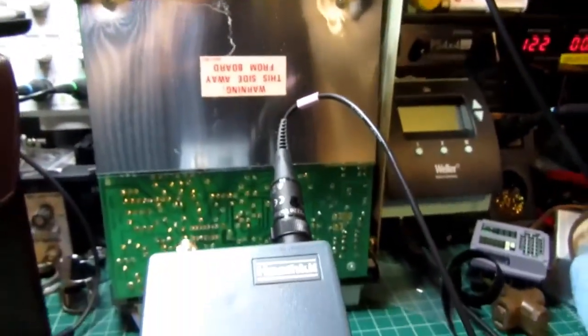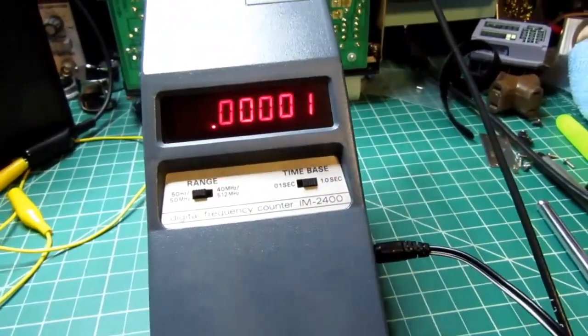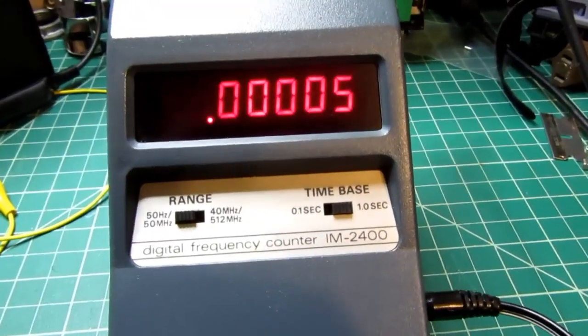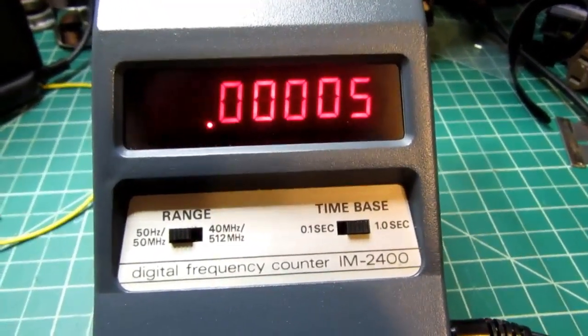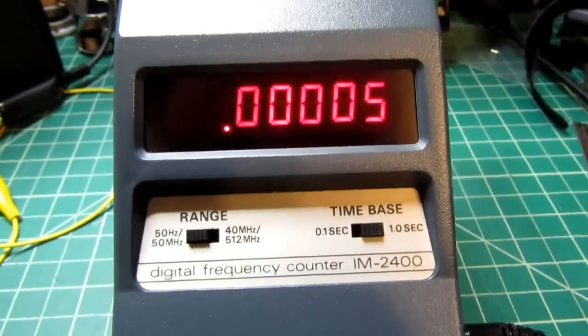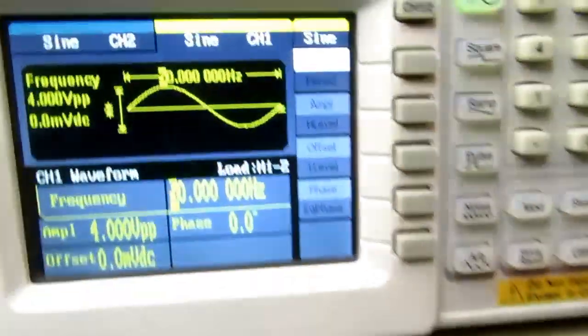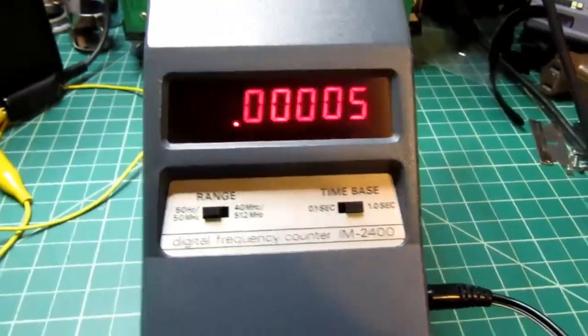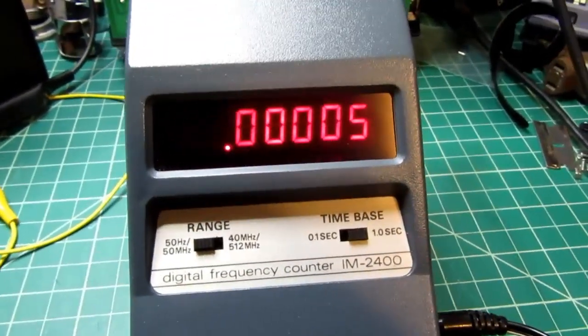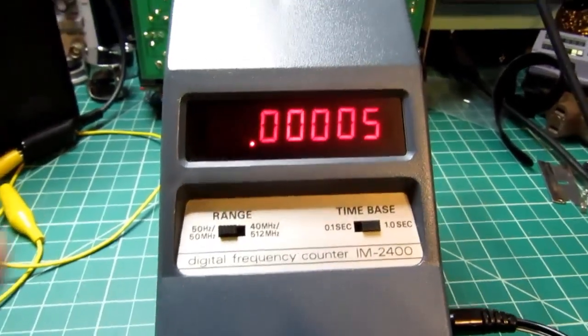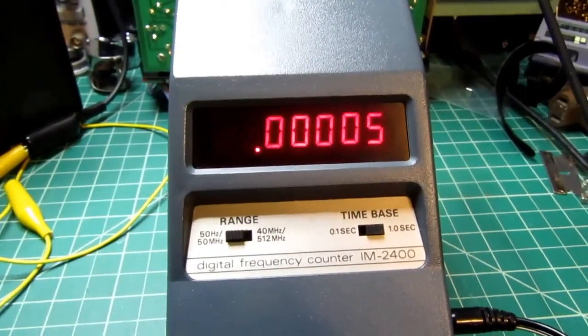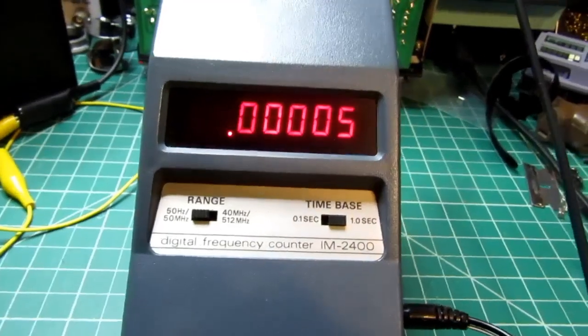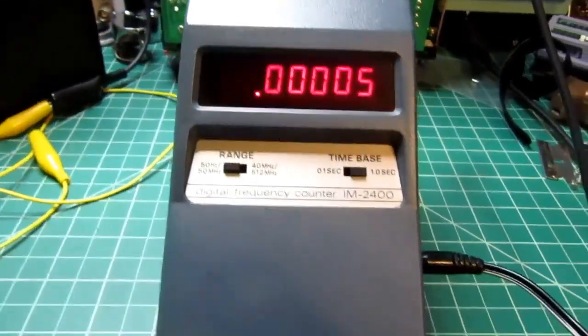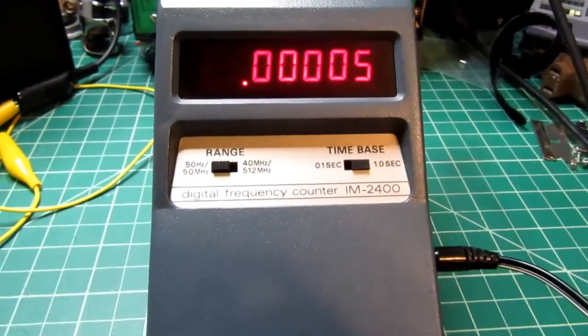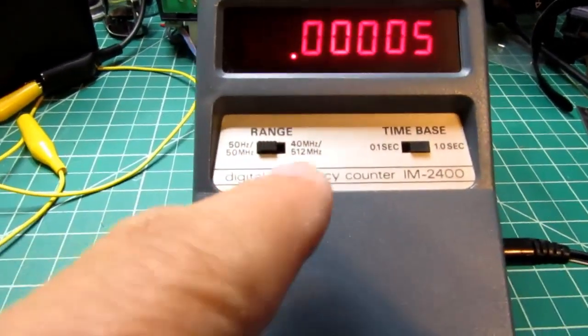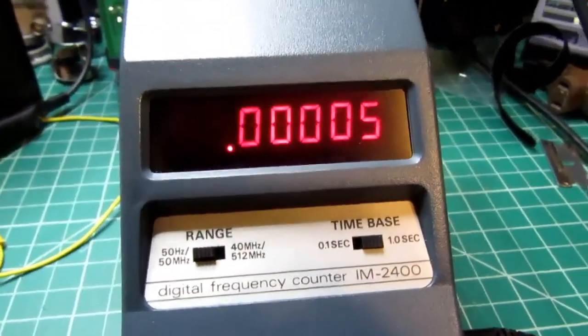And I'm going to turn the output on, and I get a reading of 0.00005 for 50 hertz. And that's the first clue that something is unusual. There is no indication on this display saying that this reading is in megahertz. You might assume it would be in kilohertz or something. It certainly isn't in hertz. Not with a range this high. You'd never get meaningful numbers with only 7 digits.